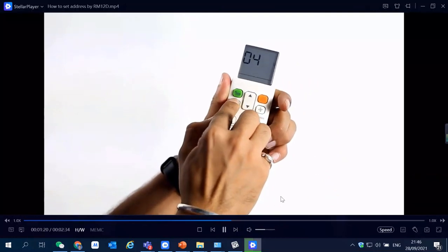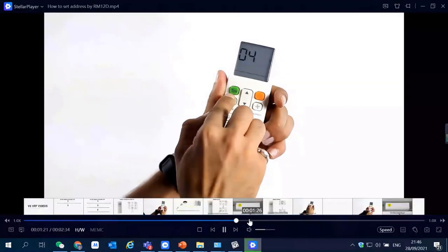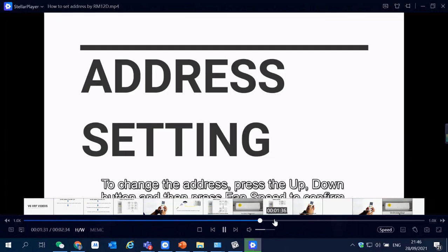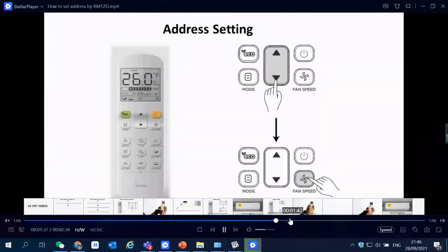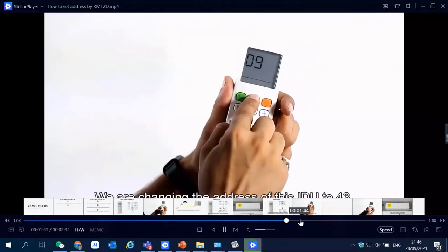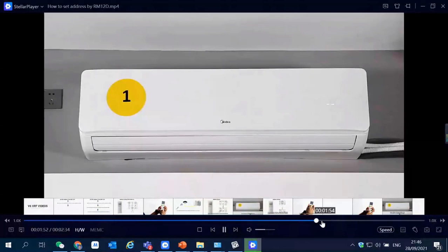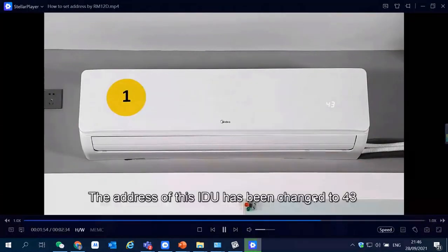You can check the address of the indoor unit, and similarly for address setting, press the up/down button to change a particular value, then press fan speed to send the address. This part is similar.